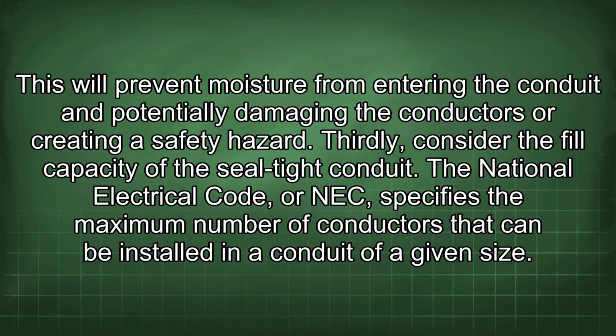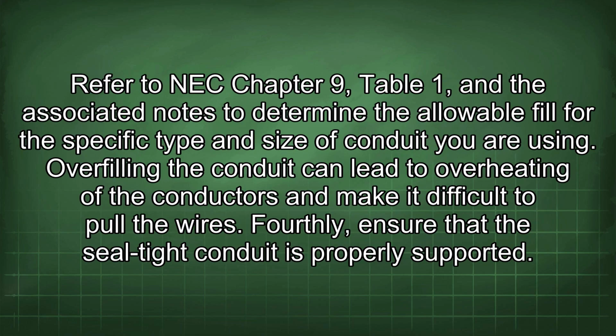Thirdly, consider the fill capacity of the seal-tight conduit. The National Electrical Code, or NEC, specifies the maximum number of conductors that can be installed in a conduit of a given size. Refer to NEC Chapter 9, Table 1, and the associated notes to determine the allowable fill for the specific type and size of conduit you are using. Overfilling the conduit can lead to overheating of the conductors and make it difficult to pull the wires.